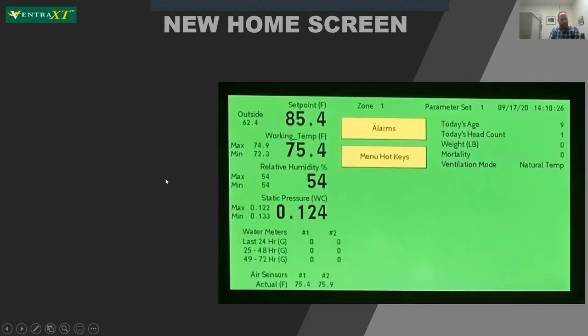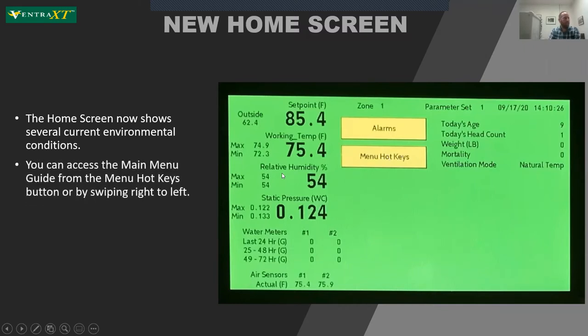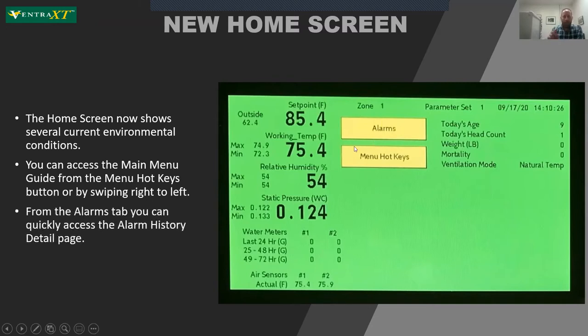Zooming in on the home screen, you can see a lot more environmental conditions at a glance right off the bat: outside temp sensor, set point, working temperature, along with min and max values for the day so far; relative humidity, static pressure, water meters, and up to 12 air sensors for each zone. At the top you have the zone, parameter set, date, time, and data you input such as today's age, head count, mortality, calculated weight. Quick step buttons to menu hotkeys give an overview of everywhere you can go, and because it's a touchscreen, you can swipe right to left to move through the top-level menu commands.